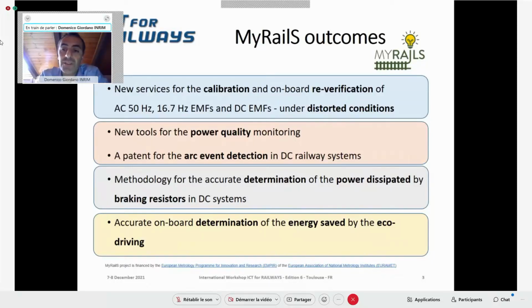Since this project involves many metrology institutes, one of the focuses was the development of new calibration services for energy measurement functions, the devices presented before by Bart that are placed on board trains to measure absorbed and generated energy. We developed calibration services for AC 50 Hz systems, for 16.7 Hz supply systems, and even for DC supply systems. The upgrade was that these calibration systems are able to apply distorted waveforms to the energy measurement functions.